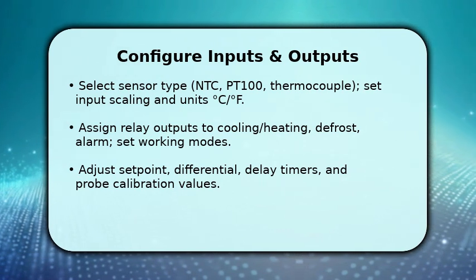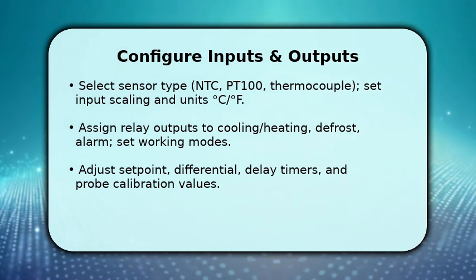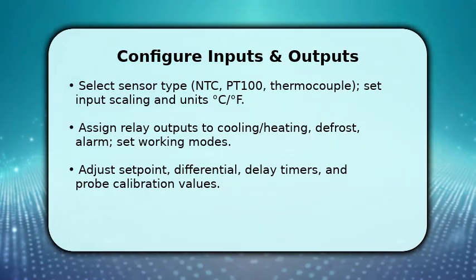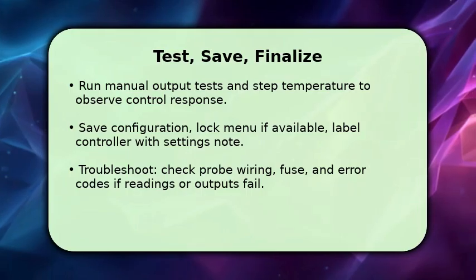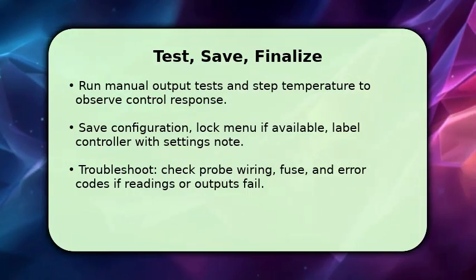Finish by testing and saving the setup. You should manually energize each output and then change the set point to make the controller drive cooling or heating. Observe that relays switch and the system responds.